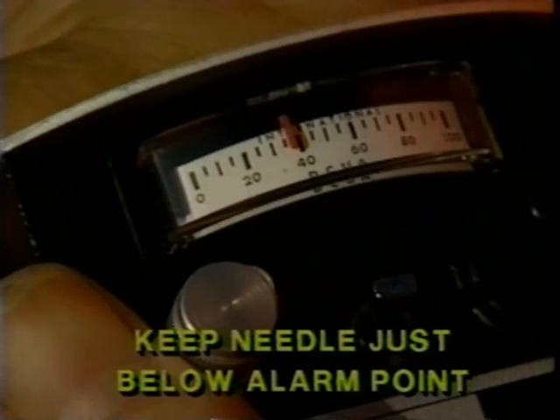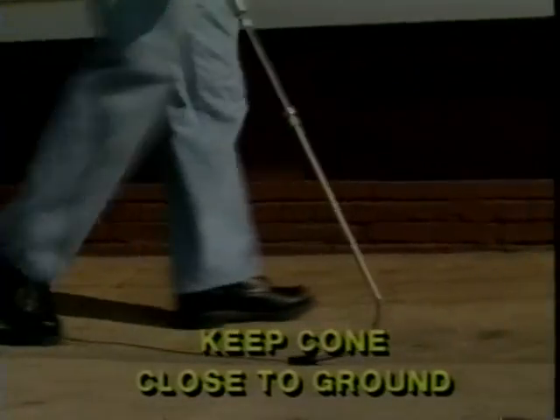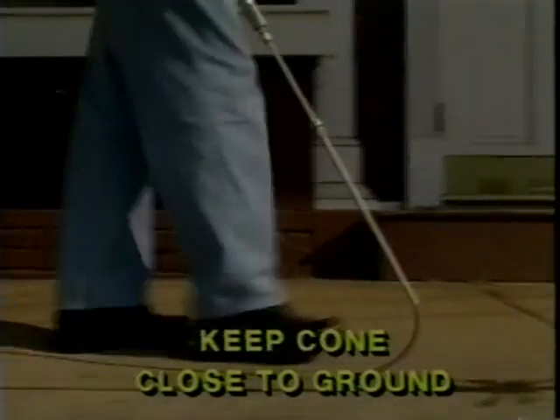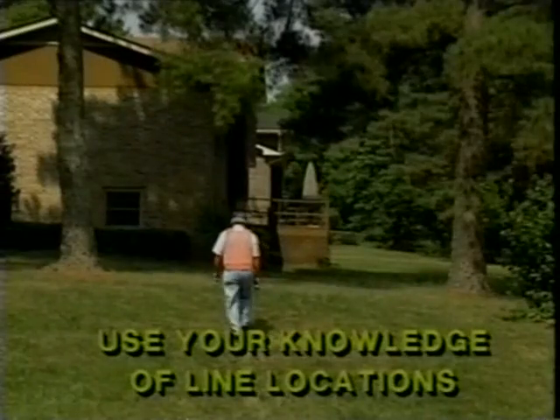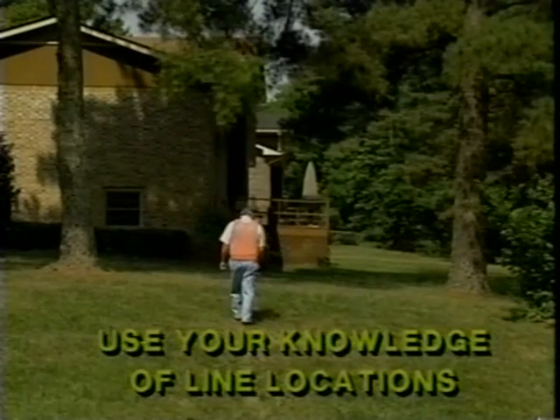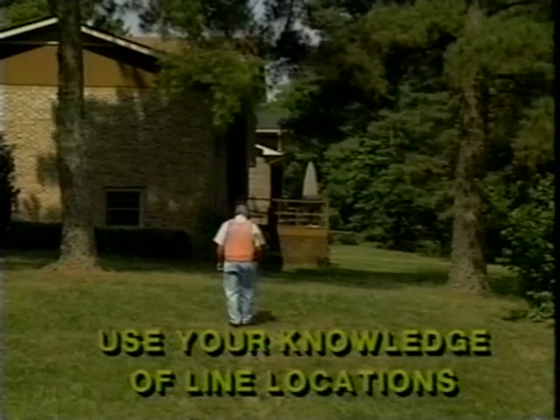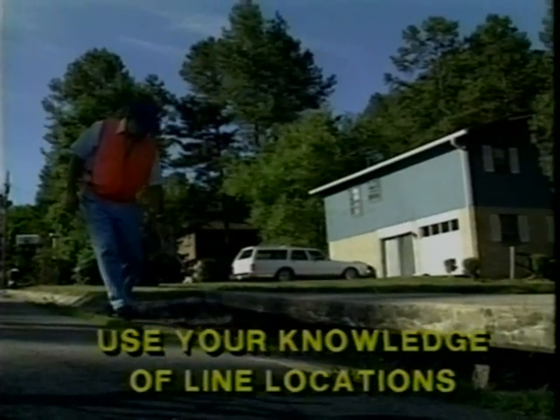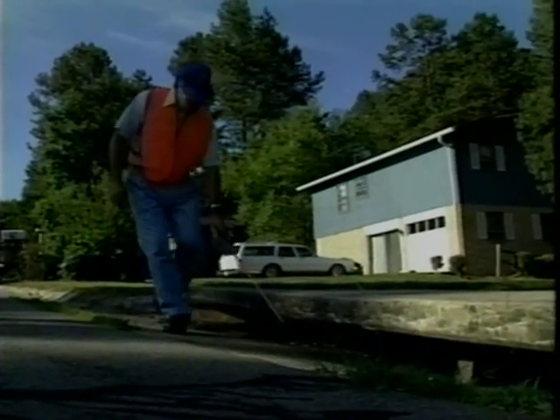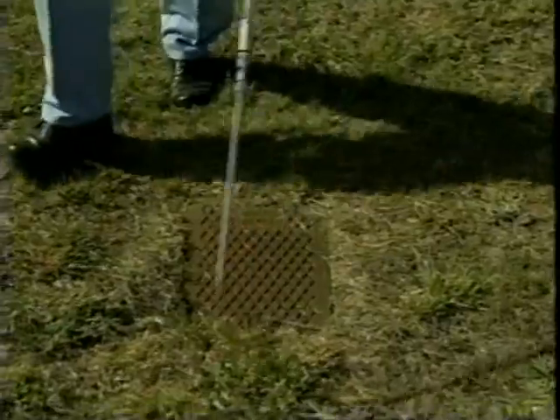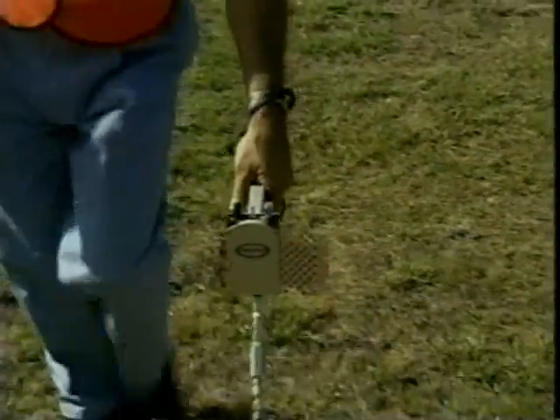1. Keep needle set to just below the alarm point. 2. Keep the cone close to the ground. 3. Use your knowledge of line locations and venting points. Specifically test all likely leak locations with special attention given to known visual indicators. If you do these 3 things, you will be assured of the most thorough survey possible.